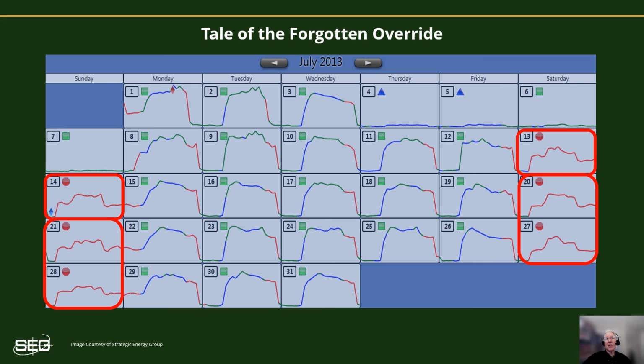Had they used the available event scheduler option for a one-time event, the override could have been scheduled to last only the 2 days it was intended for, and then it would have automatically reverted back to the normal weekly schedule again. The weekend overrides remained on for 3 months in this example, till it was finally noticed and brought to their attention. This simple oversight cost this facility an extra $30,000 in electricity. And this is a very common problem that I've seen. So periodically reviewing schedules and reviewing performance is very important for all facilities.